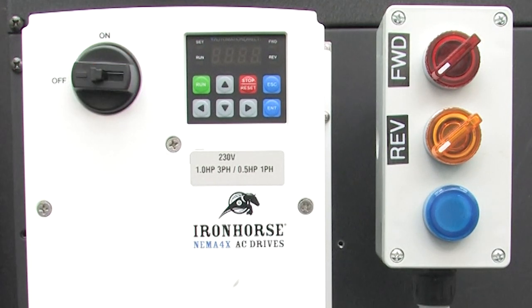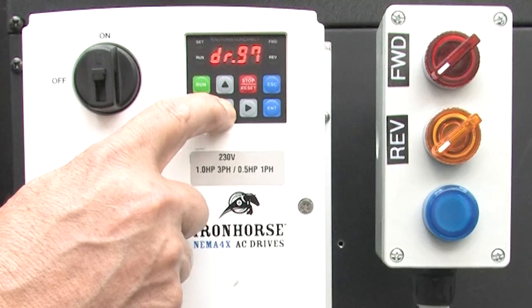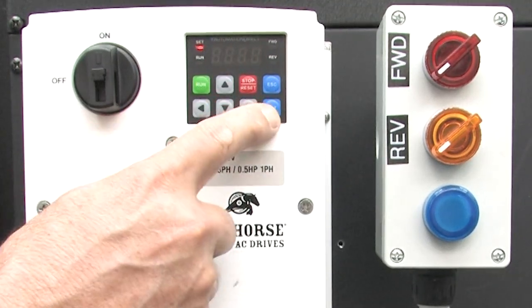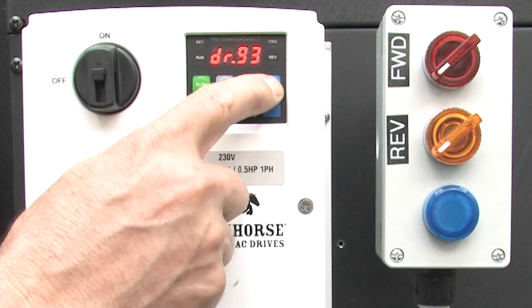I love that this NEMA 4X AC drive comes with a built-in disconnect — you can also order it without the disconnect. Let's fire this thing up and reset the drive to factory default so you know exactly where I'm starting from, by going to the drive group, parameter 93, and setting it to 1. Select that, accept it, then escape back to the frequency display.